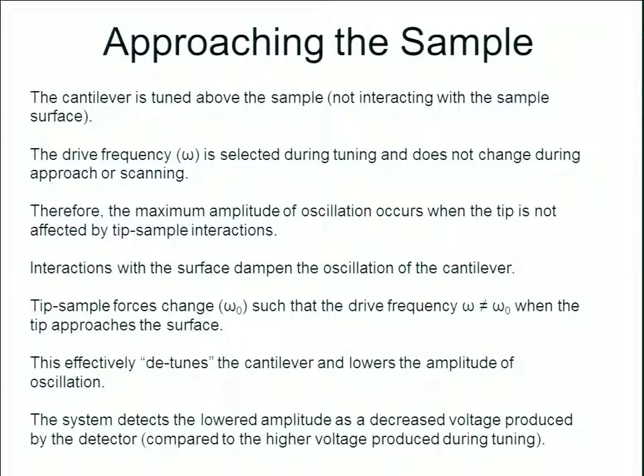When approaching the sample, you first tune the cantilever in free space and select a drive frequency during tuning. That drive frequency does not change during the approach or while scanning — you maintain the drive frequency set for the maximum amplitude of cantilever oscillation, which occurs when the tip is in free space, not affected by tip-sample interactions.